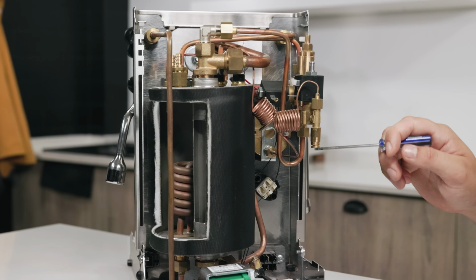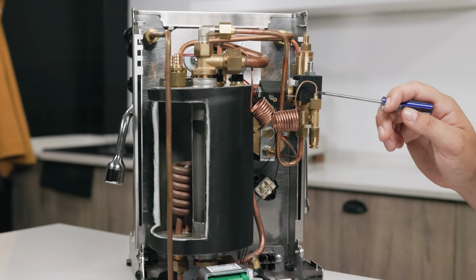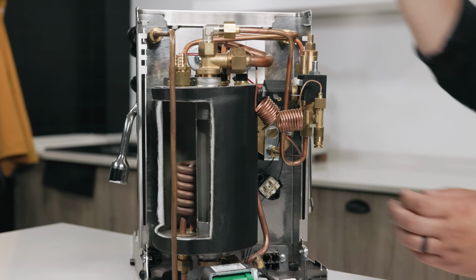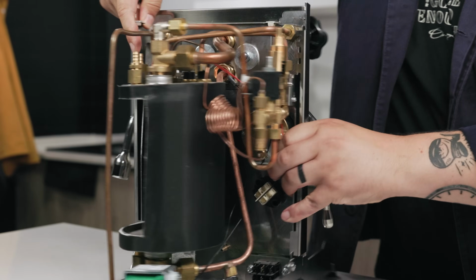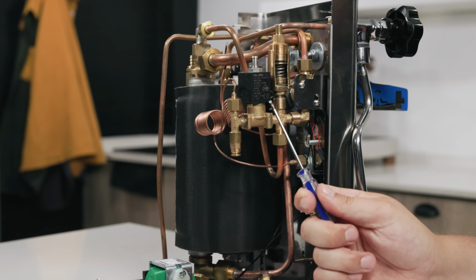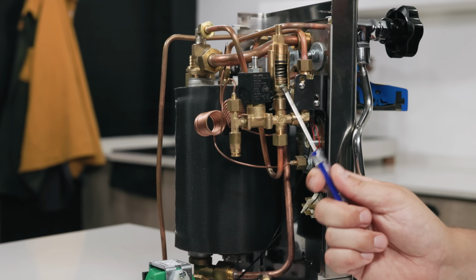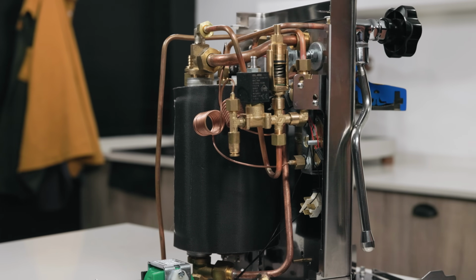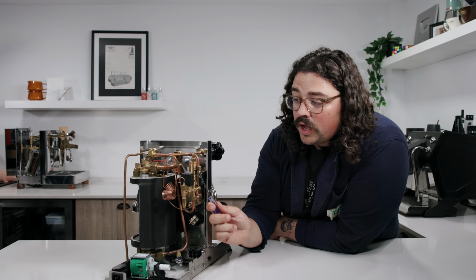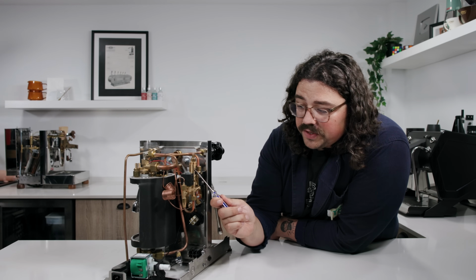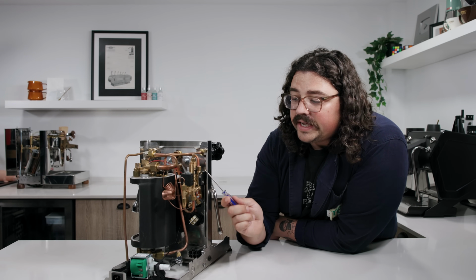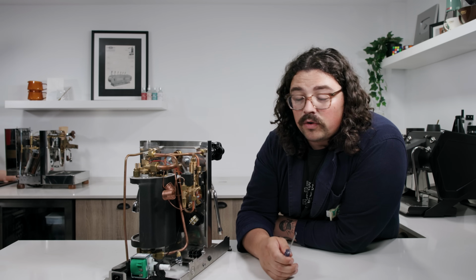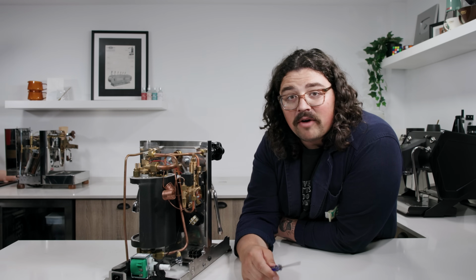So it pumps up into here, into this system. This takes a reading and goes through there. Then as it continues through, it goes through the solenoid, which is right here, and then here's the overpressure valve. Now for a vibratory pump, this is incredibly important. Whatever tension this spring is set to is going to dictate the maximum pressure coming out. All right, so these pumps usually go up to about 15 bar.